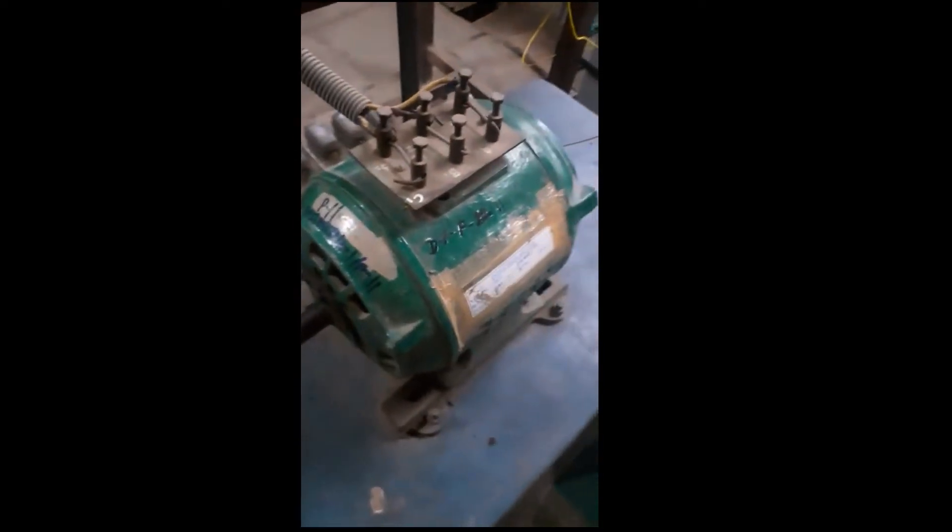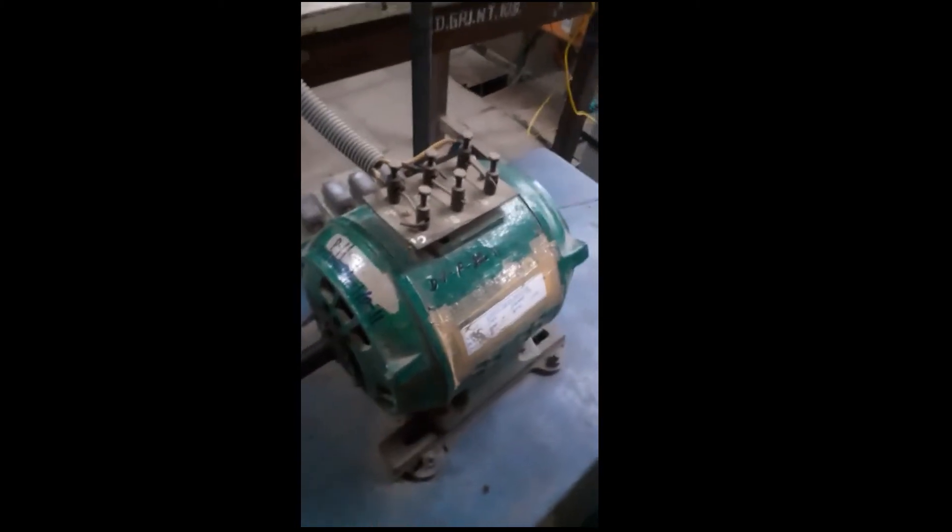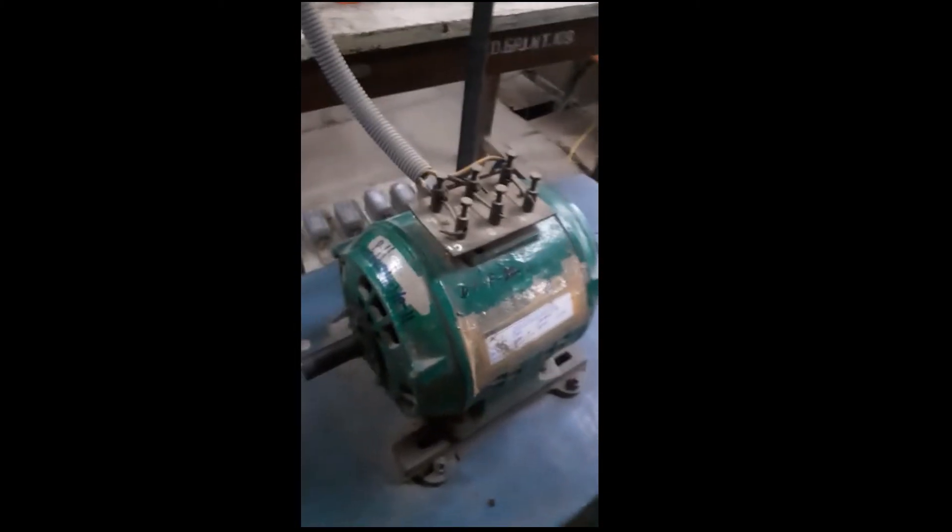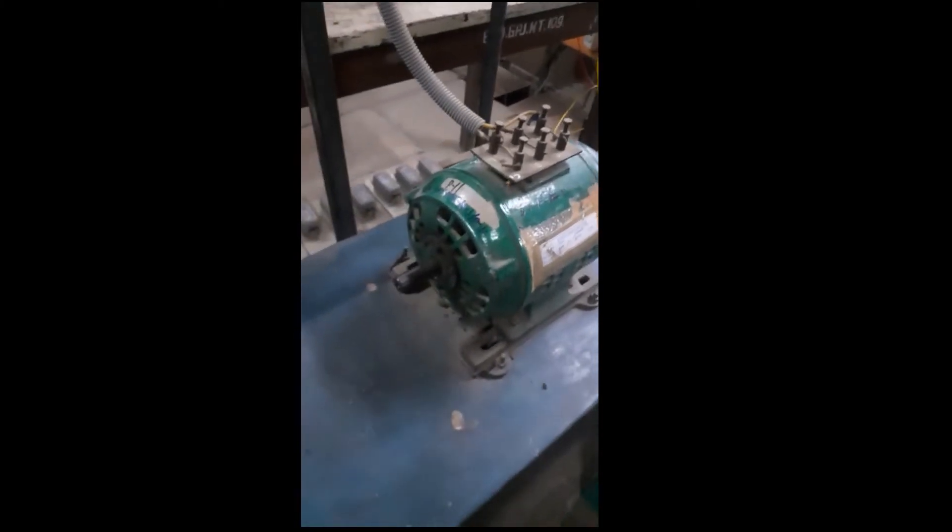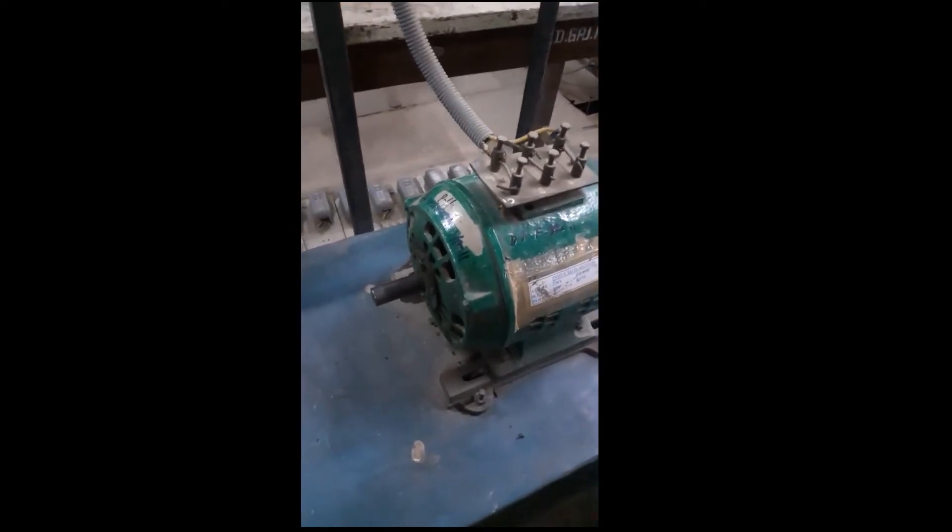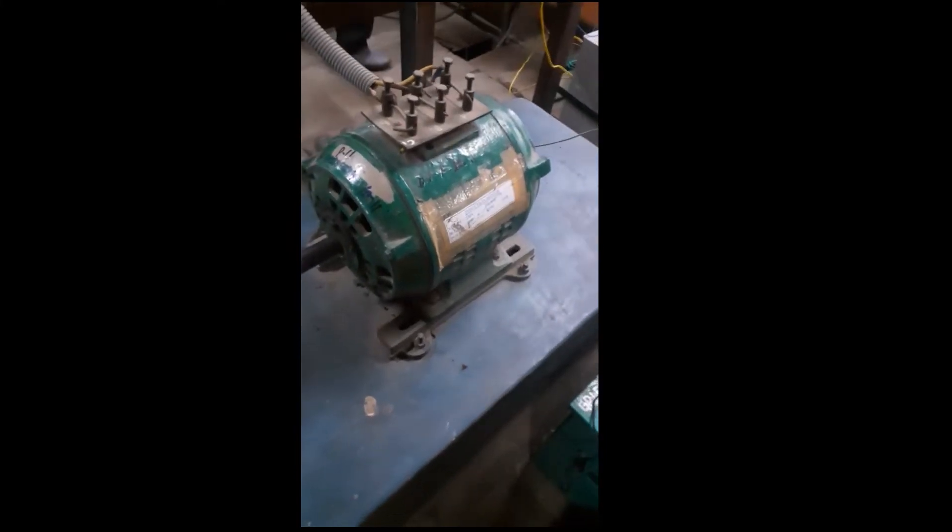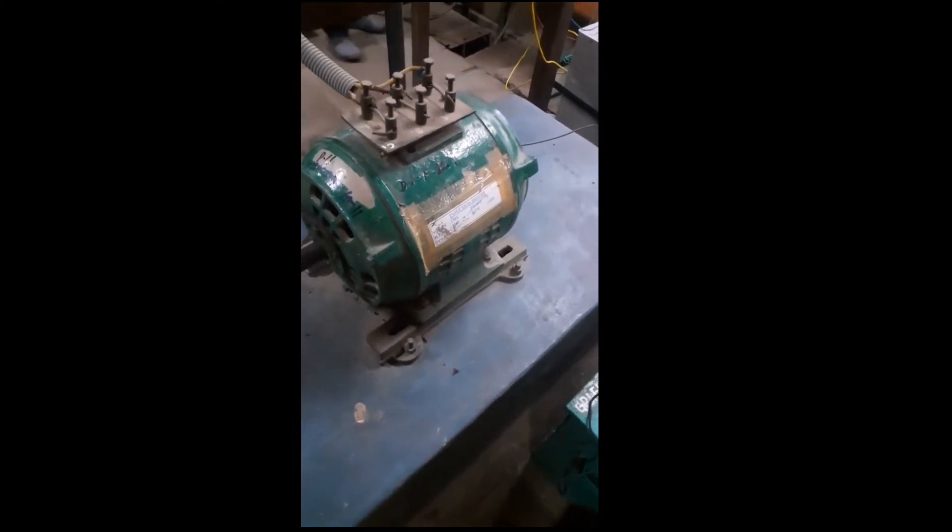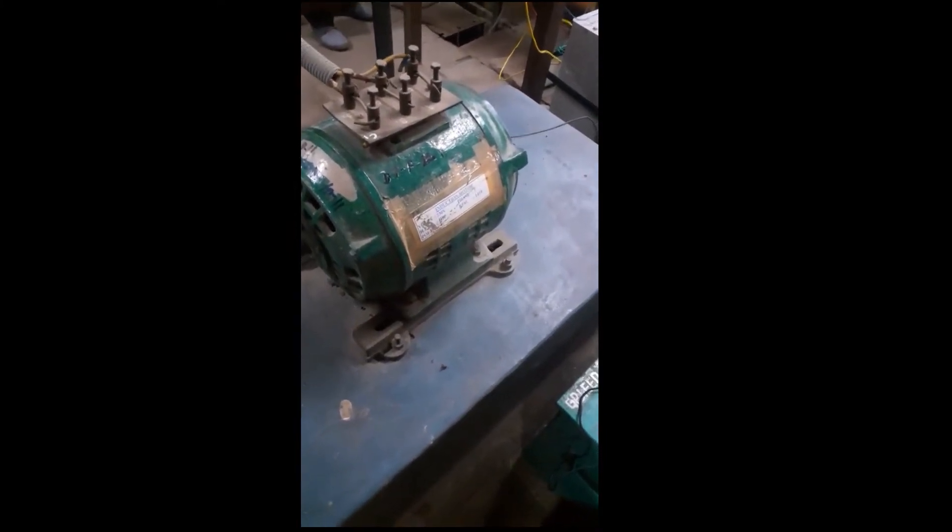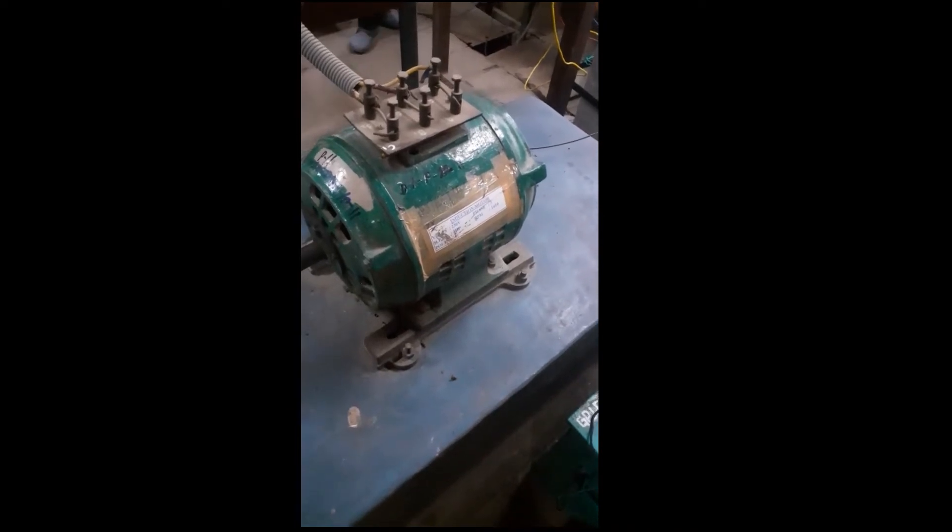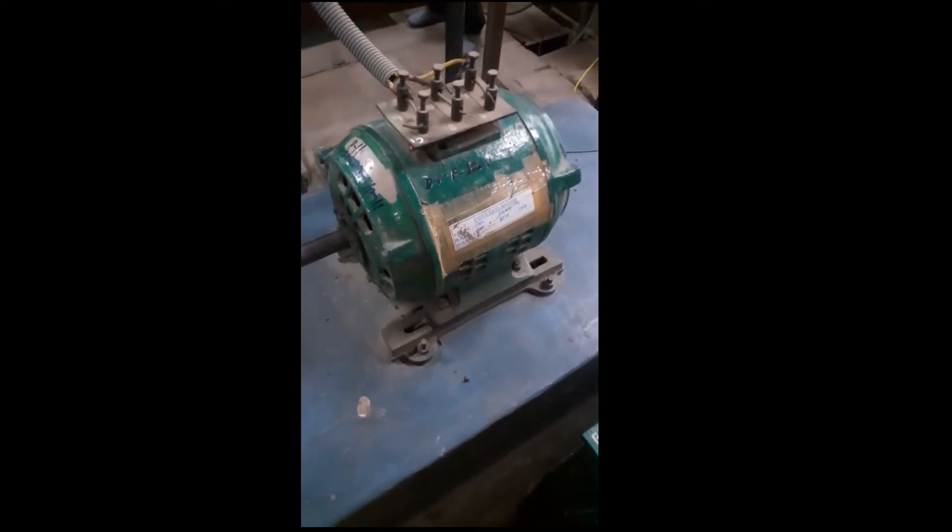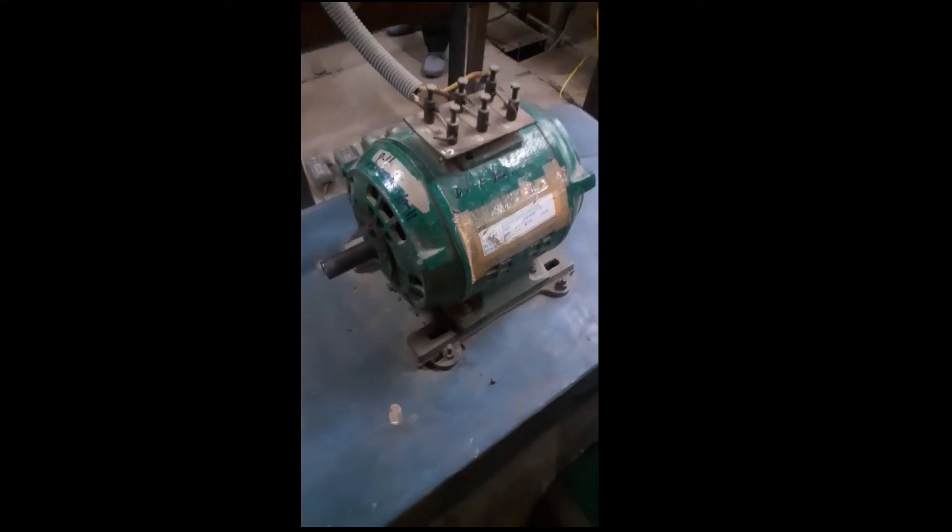To conduct this particular reduced voltage running up test, we have to apply reduced voltage. This motor is rated for 230 volts, but 1 by root 3 times that rated value—that is 230 divided by root 3—comes to 132 volts. So we have to apply 132 volts across the input terminals of this particular induction motor.